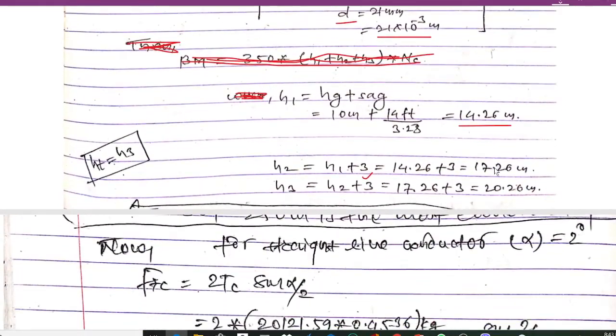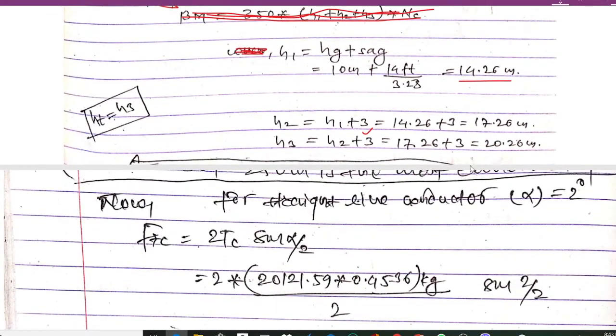The vertical spacing between conductors is 3 meters, so h1, h2 = h1 + 3, and h3 = h2 + 3. Since the question specifies straight line towers, we use alpha equal to 2 degrees for the deviation angle.